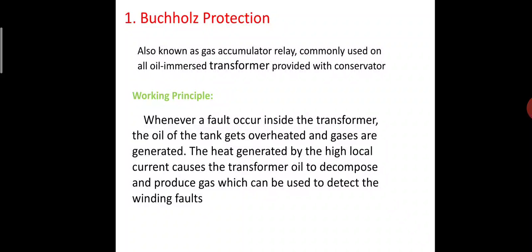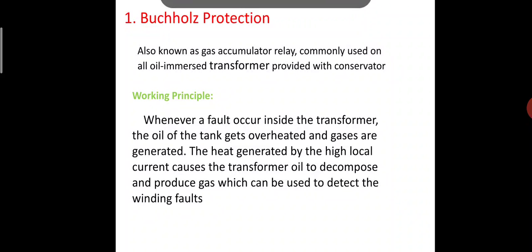And limitations of Buchholz relay: it can be used only for transformers with conservators. Only faults below oil level are detected. These are the Buchholz relay construction, working principle, advantages and limitations.